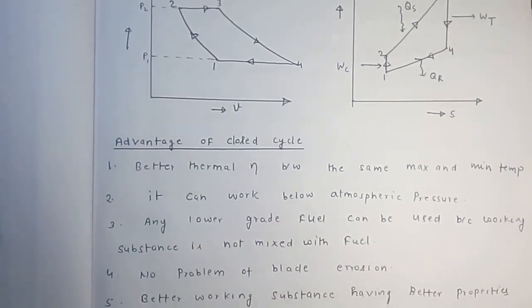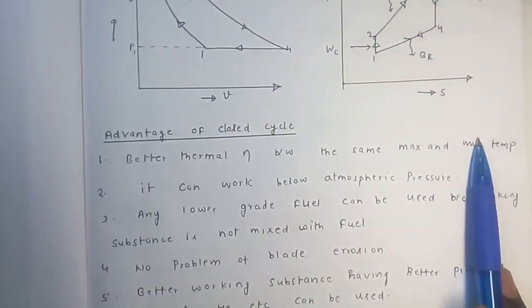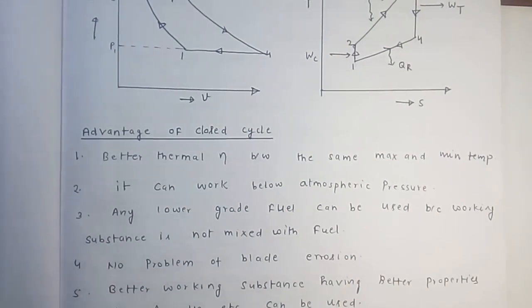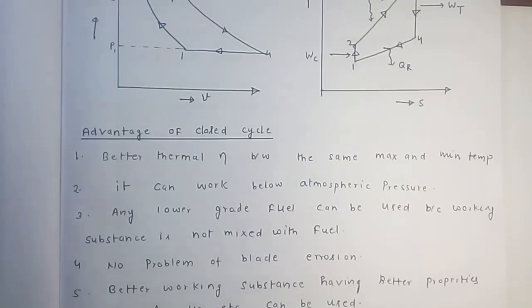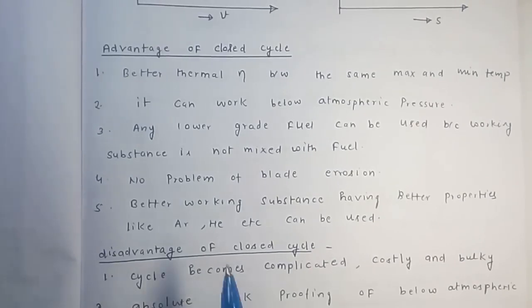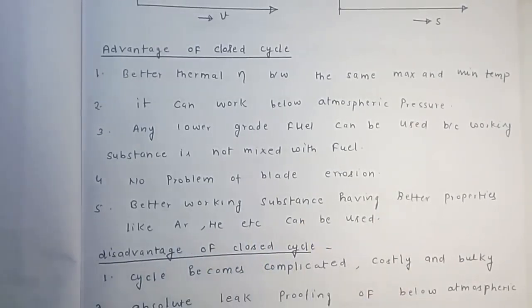To summarize the advantages of closed cycle: better thermal efficiency between same max and min temperatures; it can work below atmospheric pressure; lower grade fuel can be used since the working substance is not mixed with the fuel; no blade erosion problem; and we can use better working fluids like helium or argon, which improves thermal efficiency further.